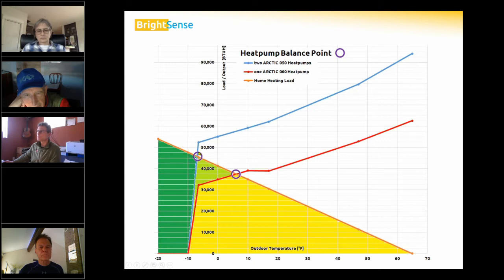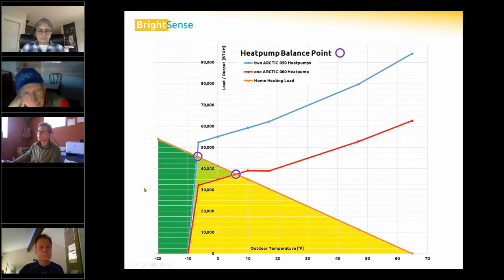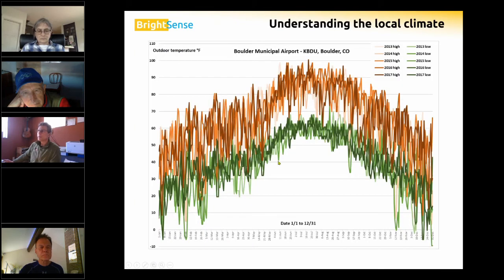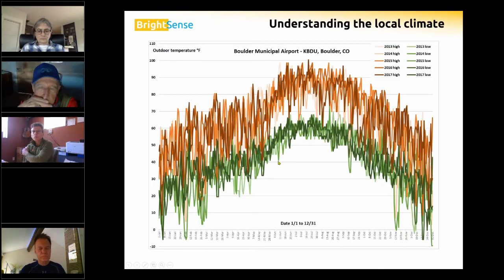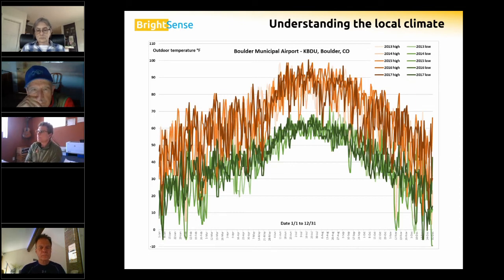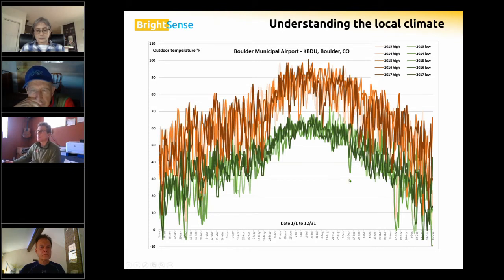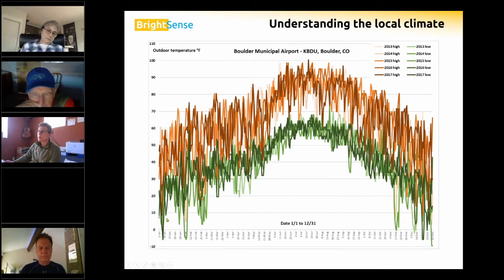The larger 60-unit model would be able to deliver energy below zero degrees, down to about minus seven. When doing an analysis and trying to fit a heat pump to a home, we need to look at local climate — what temperatures will we experience at that location?